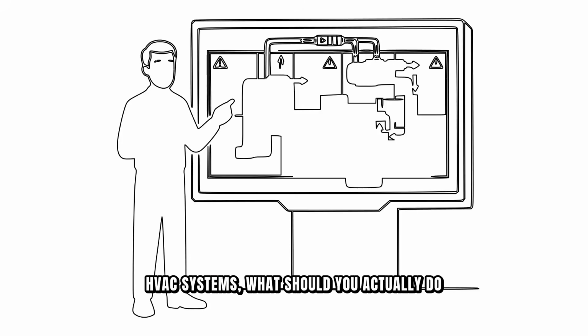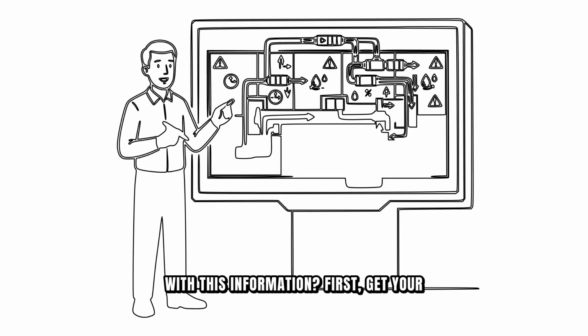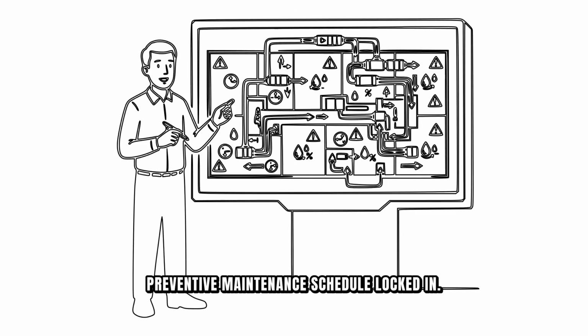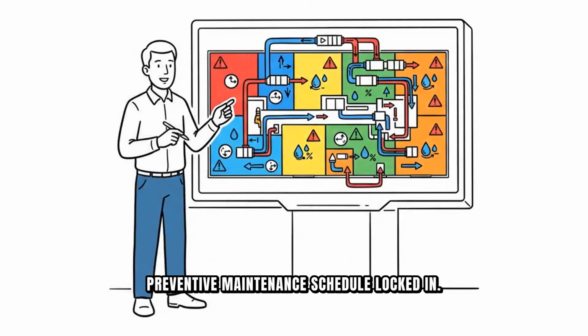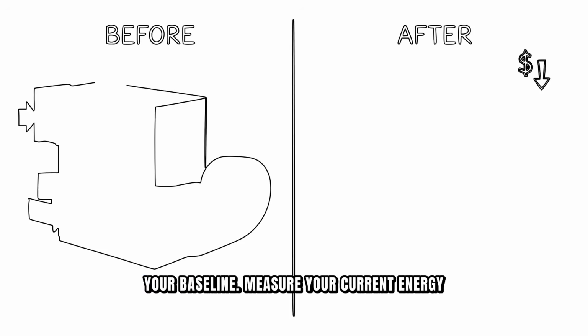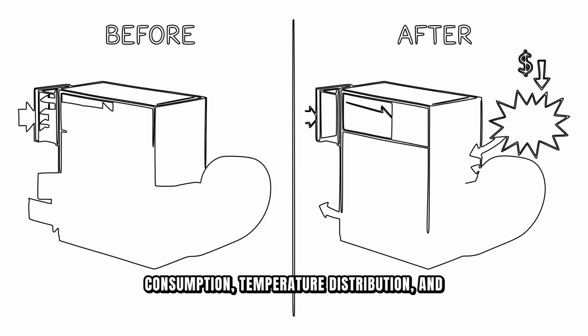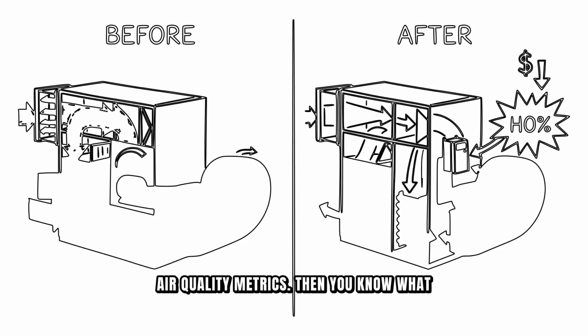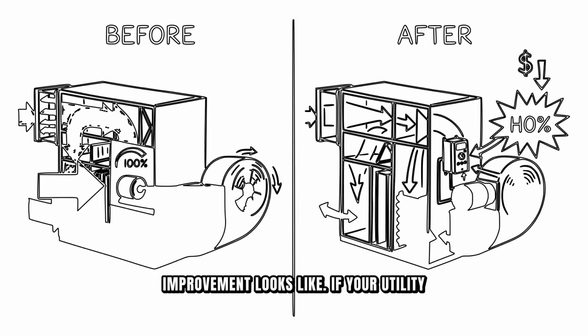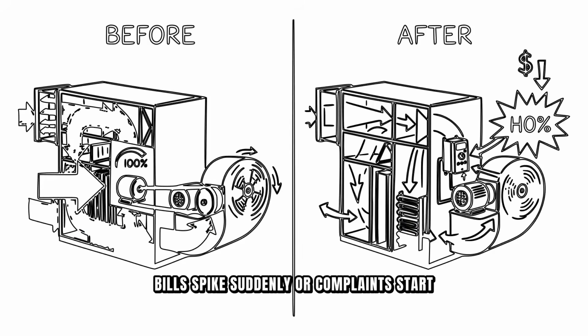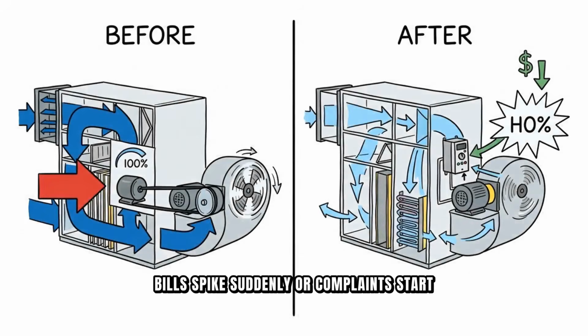Let's circle back to the practical side for a moment. If you're responsible for building HVAC systems, what should you actually do with this information? First, get your preventive maintenance schedule locked in. Filter changes, coil cleaning, drain flushing, and sensor checks should be on a regular calendar. Second, understand your baseline. Measure your current energy consumption, temperature distribution, and air quality metrics. Then, you know what improvement looks like.